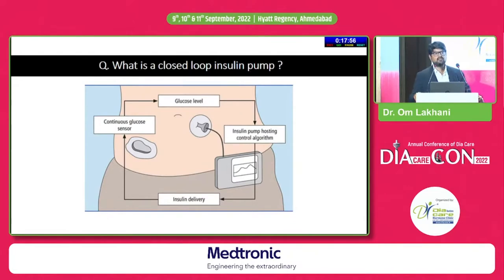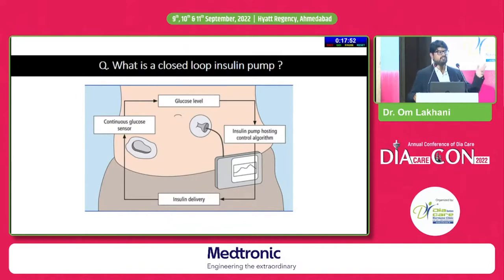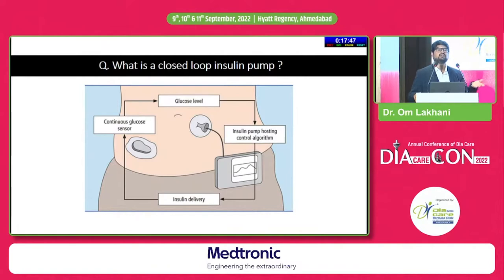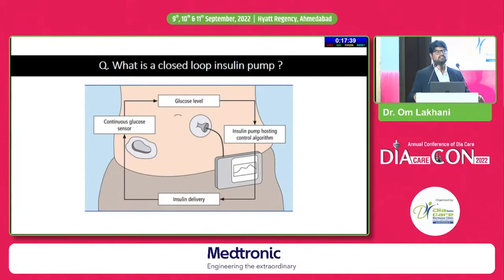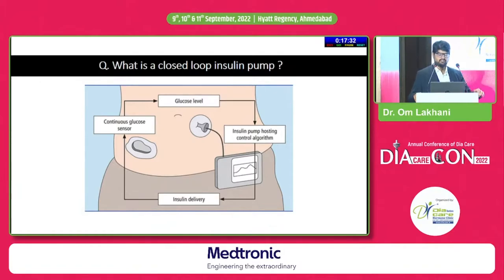A real-life example of a closed-loop device is your air conditioner. You switch it on, set the temperature to, say, 26 degrees. If the temperature increases, the air conditioner starts and brings it down. If the temperature reduces, it stops. The same way, a closed-loop device senses glucose through the CGM and communicates with the pump to deliver insulin.